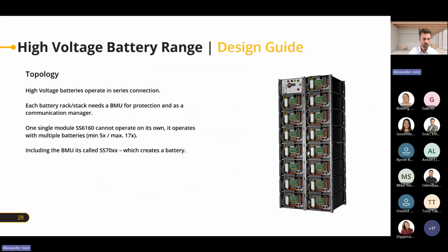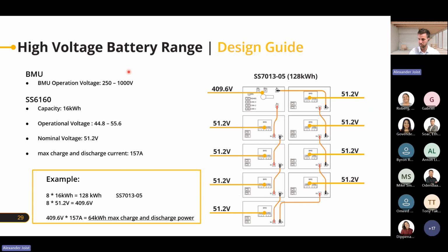If we now go into the calculations and explanation, we know our BMU has an operating voltage of 250 to 1000 volt. Now, if we take the example of the SS7013, 128 kilowatt hours, we have 16 kilowatt hours per battery module. Our nominal voltage is 51.2 per battery module. Our max charge and discharge current is 157. So now we know that these connected together come to a total of 409 volt. We just add, because it's a series connection, it's not parallel like the low voltage before. On the high voltage, we have a series connection. So now we have 400 volt with 157 amps.